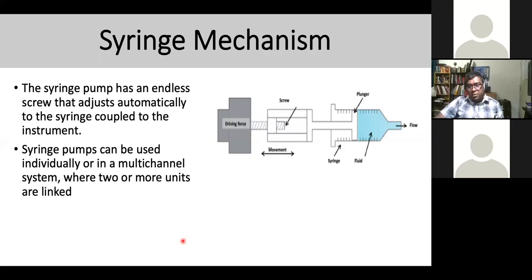Syringe mechanism is using an endless screw that adjusts automatically to the syringe coupled to the instrument. You can see the endless screw with the movement line that is moving the syringe and forcing the pressure to create the flow. So it can be used individually or as a multi-channel system. One of the things you can do is use multiple channels, more than one syringe pump. In some cases you're going to use more than five. So that's how the system works.